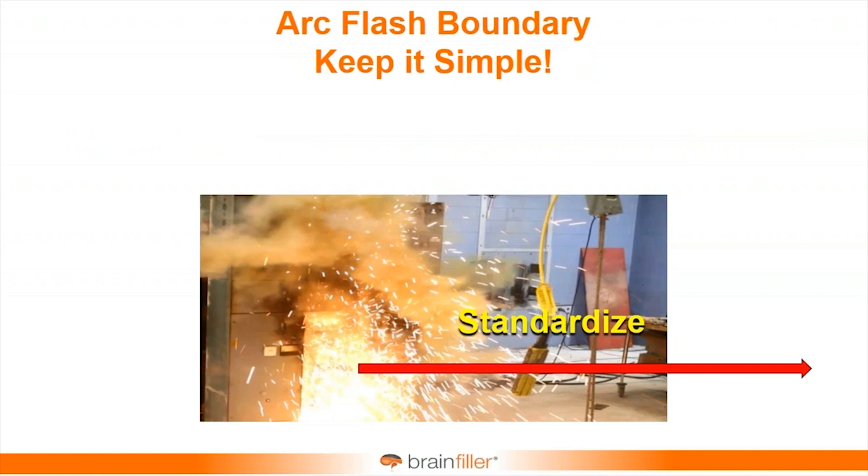I first introduced this concept back around 2004 at a conference I was speaking at. I mentioned just selecting eight or ten feet — something large. A few people looked at me like that was extreme. But I said it really only affects the person that doesn't belong there, so just get them out of the way. It does maybe affect where you put on your PPE when entering the area, but once you open the doors and have the arc flash hazard, you're doing that anyway. So eight or ten feet is not such a bad way to go.